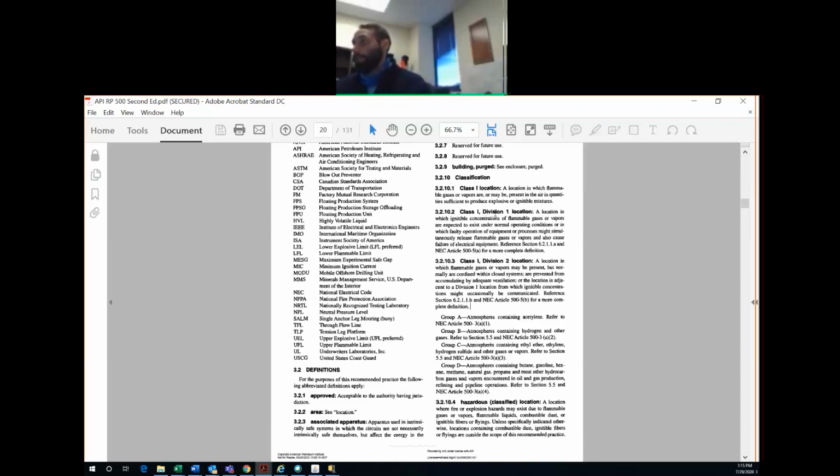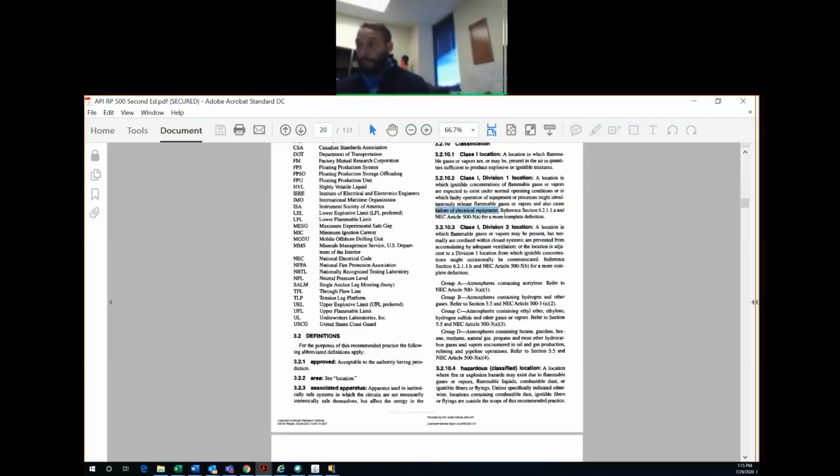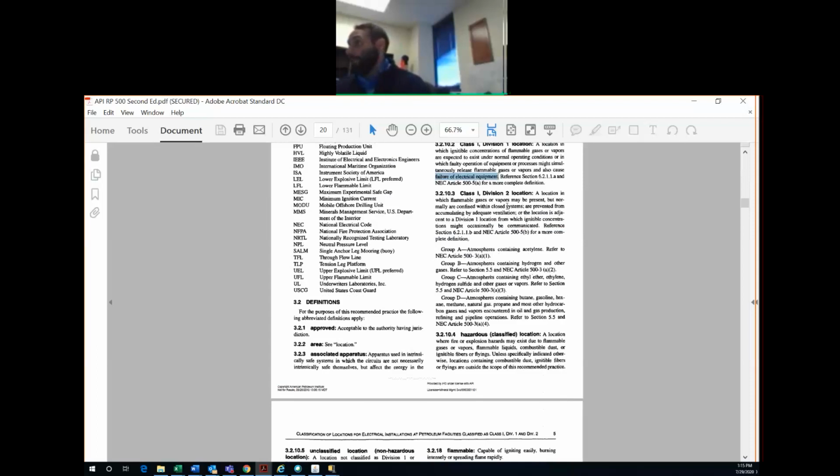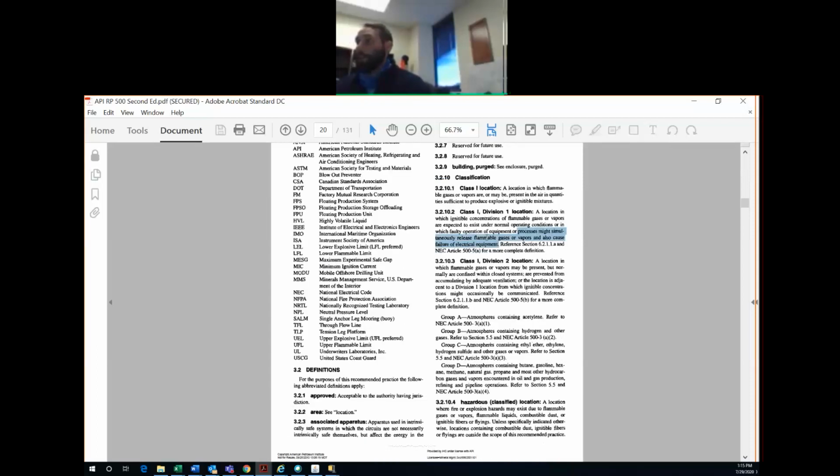so that's interesting because they're saying not only is it a location where it exists under normal operating conditions, but also where if there's an actual faulty piece of equipment that causes a failure of electrical equipment, you got to call that Class 1 Div 1 too. I haven't seen a ton of examples that meet that second criteria.